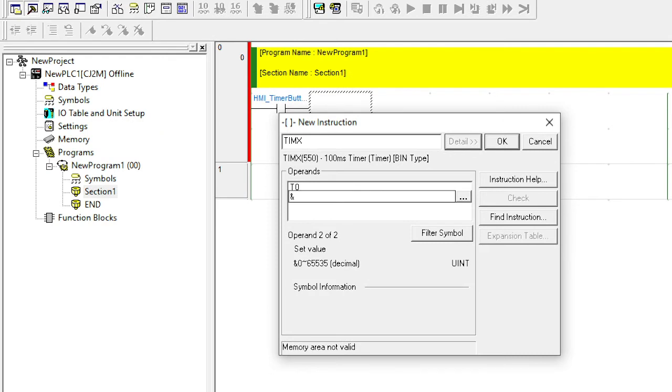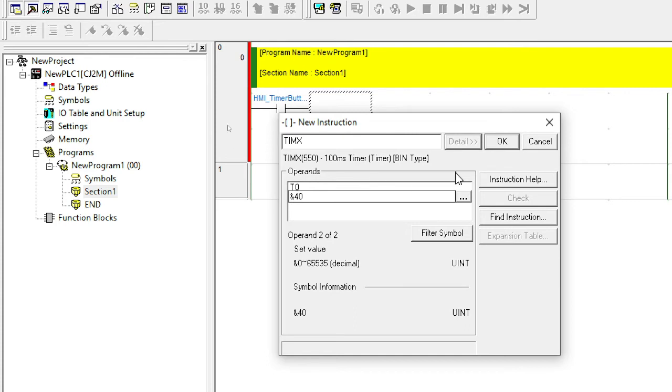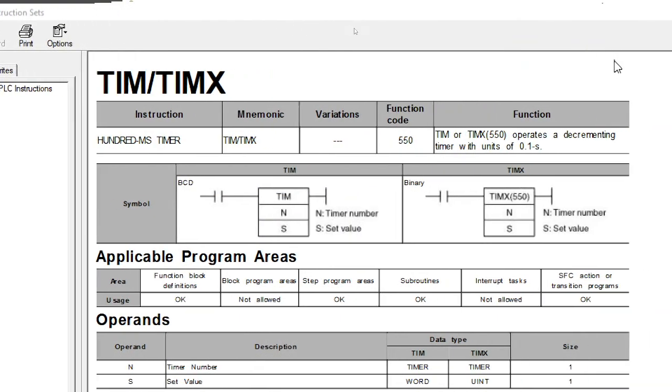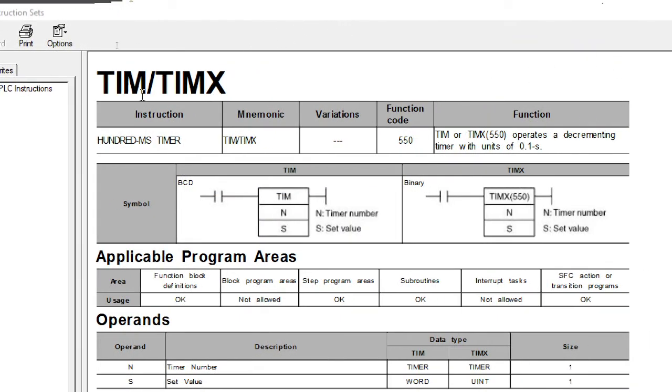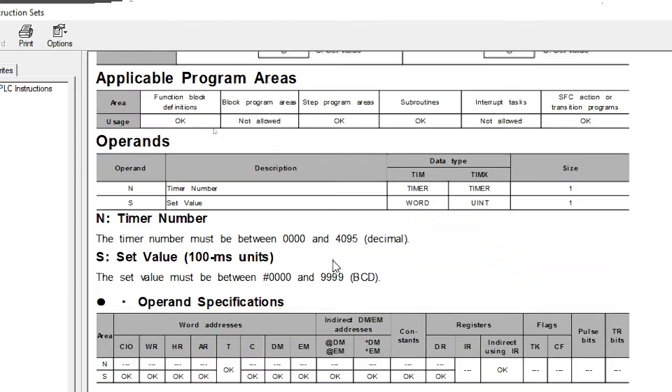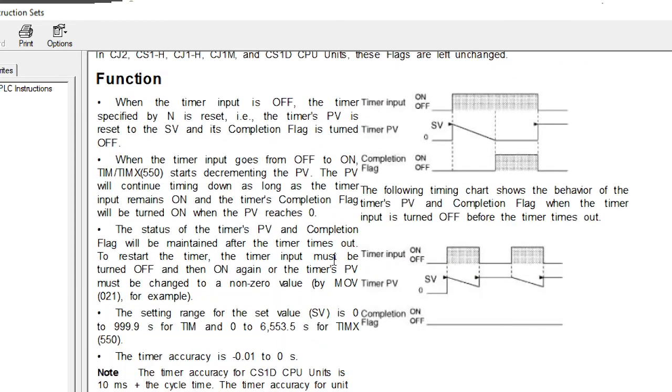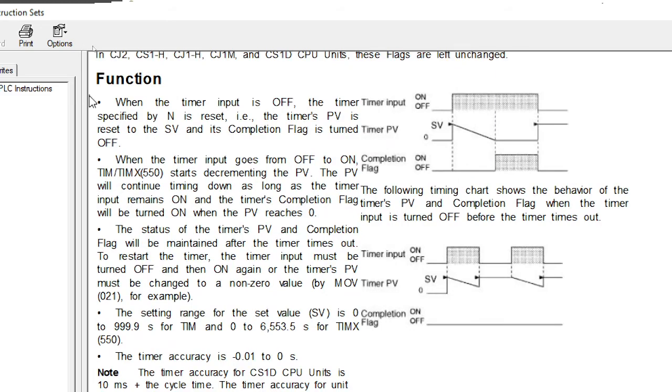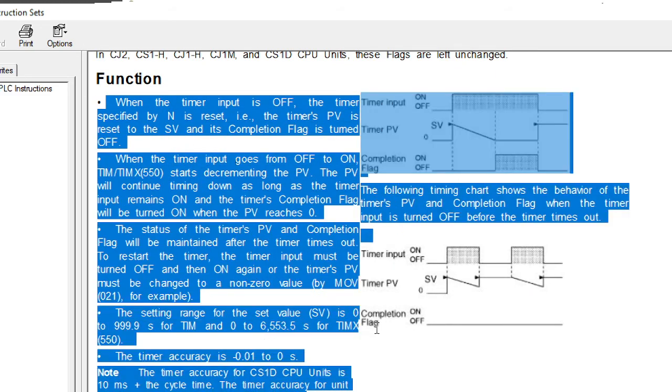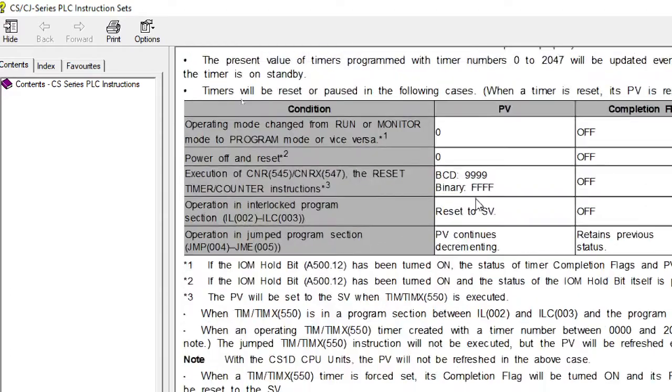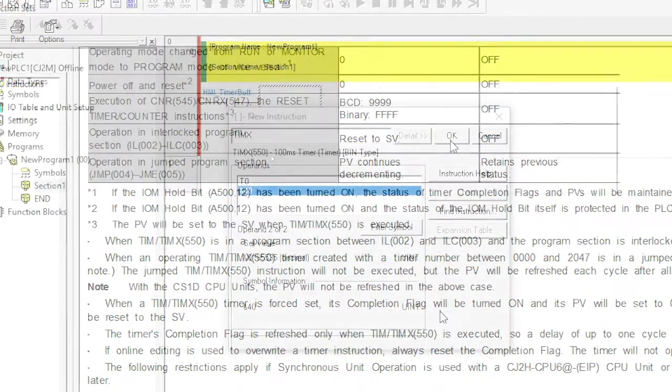Select down one more. And I need to set the value. So in this case, I want my timer to run for four seconds. So you're told here in the text, it's 100 milliseconds per tick. And there's 1,000 milliseconds in one second. Therefore, if I put in 40, that'll be four seconds. I also have the option here to select Instructional Help. If I do that, the instructions for T-I-M and T-I-M-X come up. And it tells me here that a T-I-M-X takes a binary value and a set value. So this is very useful if you're not too sure how to use the function.